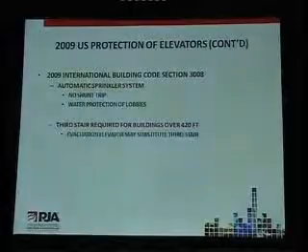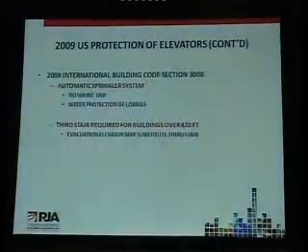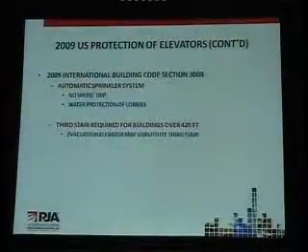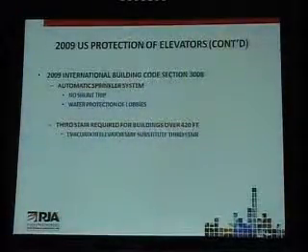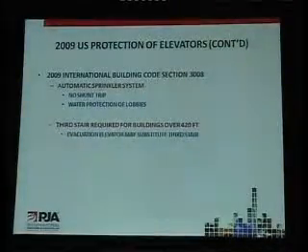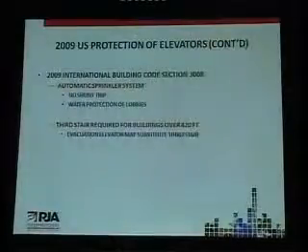This stair cannot be used for a means of egress. Therefore, if you are thinking that you can add a third stair and increase the occupancy of your building and get those benefits, no. You basically need to add this third stair without any other benefit than protecting firefighters. So you can get alleviation from this requirement by implementing this elevator evacuation system.